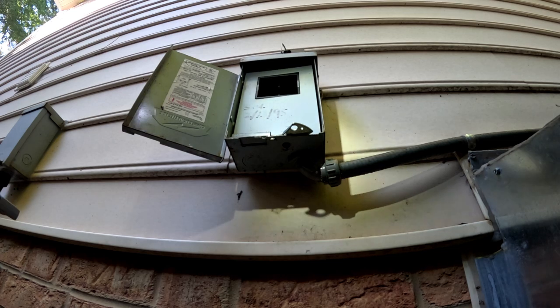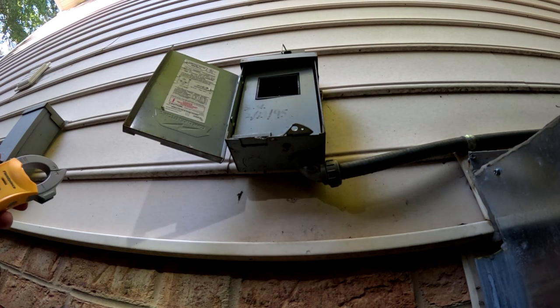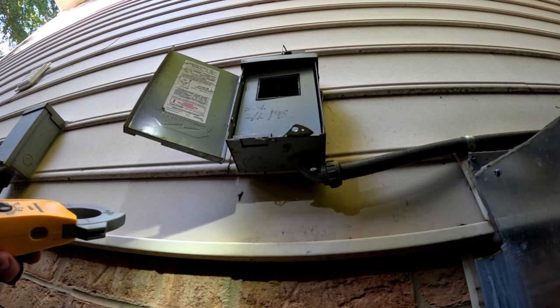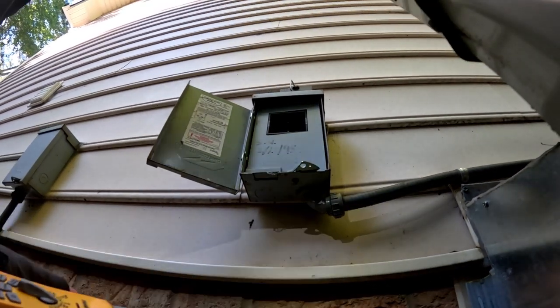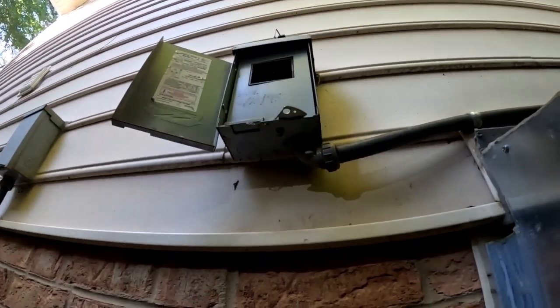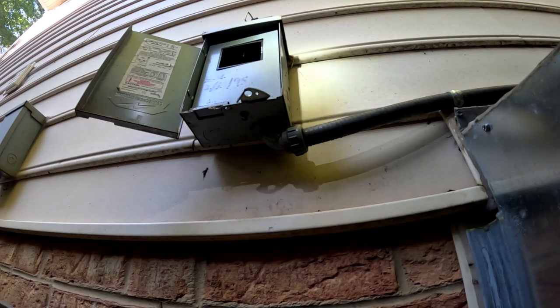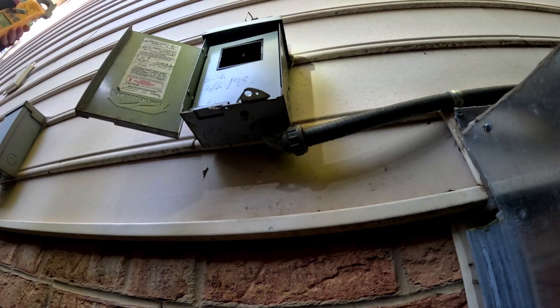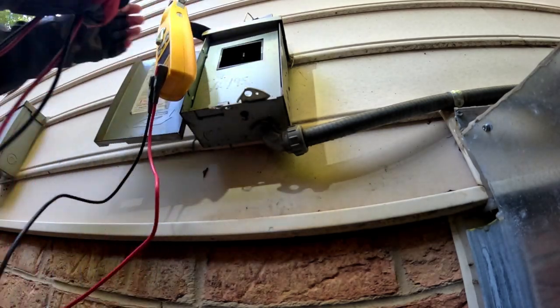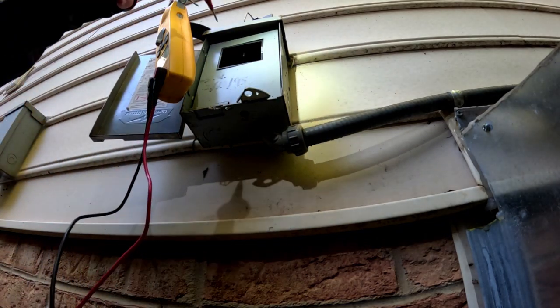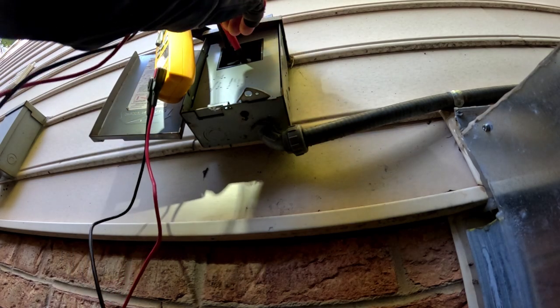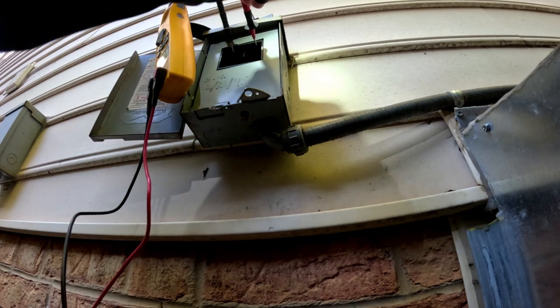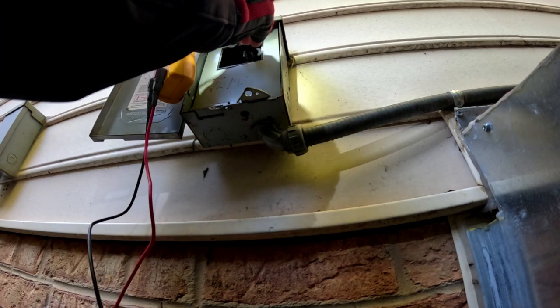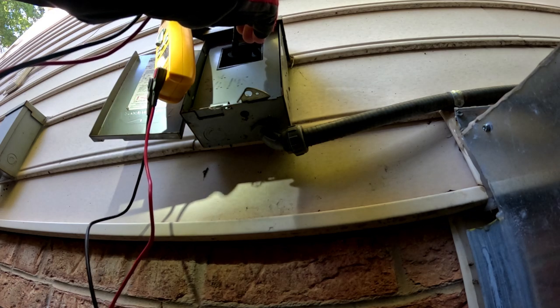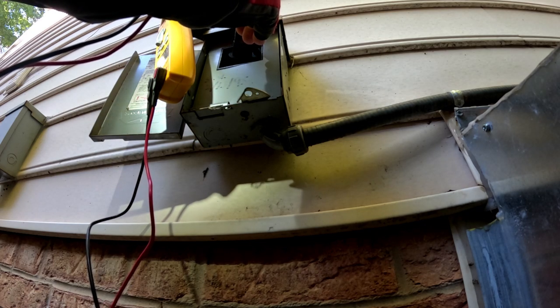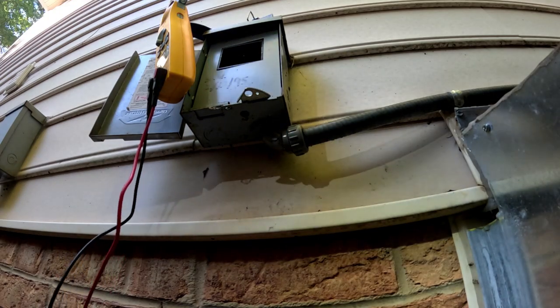Alright, first thing I'm going to do real quick is check the disconnect box and see if I have voltage, because that should have, I would think, tripped the breaker. And I'm in leaves over here, so trying to keep the camera balanced is a little difficult, but anyway, let's see what kind of voltage we've got in this disconnect box. I would think a high voltage wire hitting that fan wheel would have tripped the breaker. Nothing on the bottom, and okay, no, I've still got 246 volts at the disconnect box, so it didn't trip the breaker.